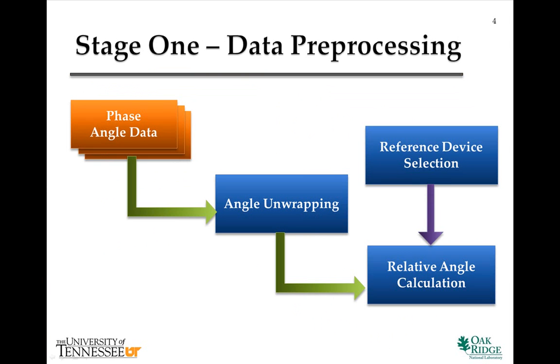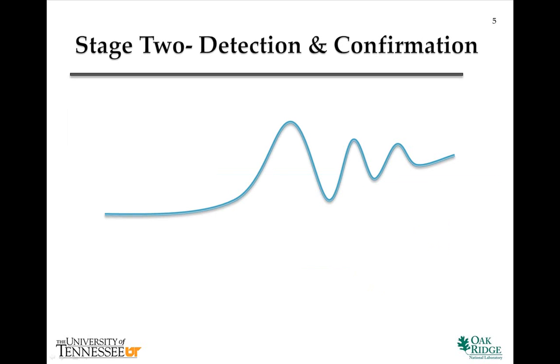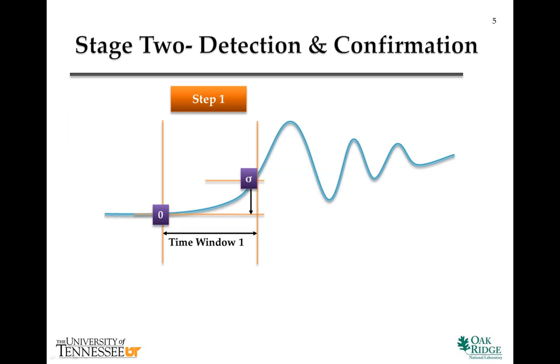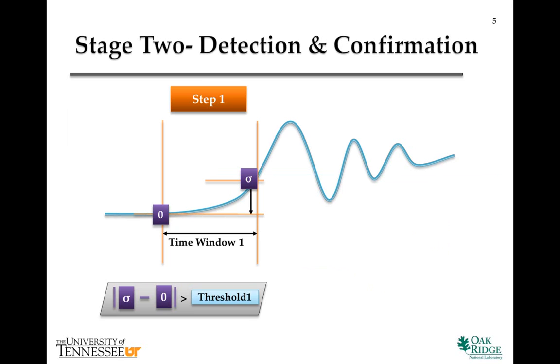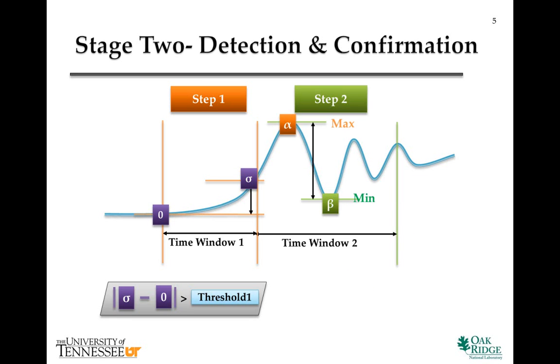There are two stages for the FNET oscillation detection. The first stage is data preprocessing, where phase angle unwrapping and relative angle calculation will be performed. The second stage is oscillation detection and confirmation. First, the program calculates the absolute angle change within the first time window for each device. If it is over a certain threshold, detection is triggered.